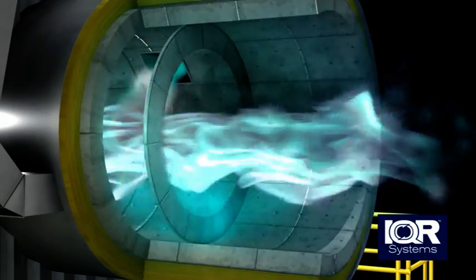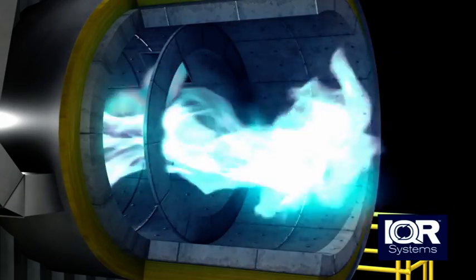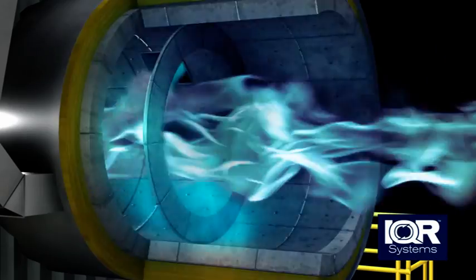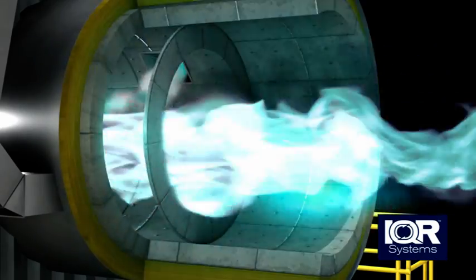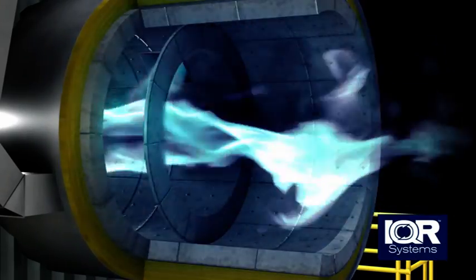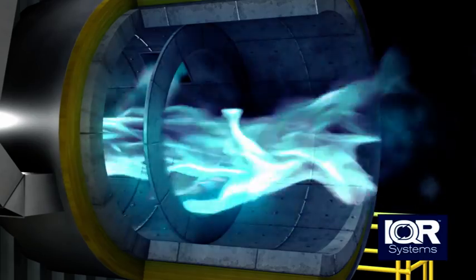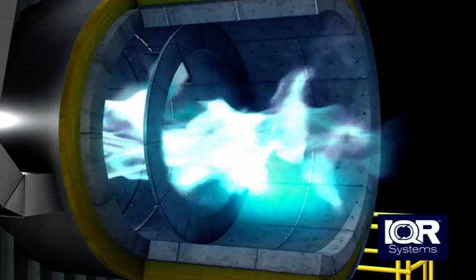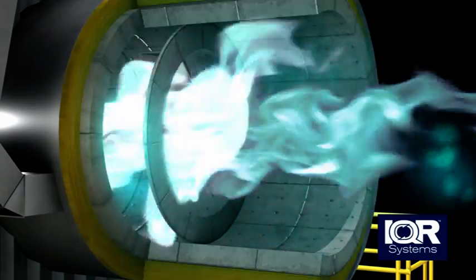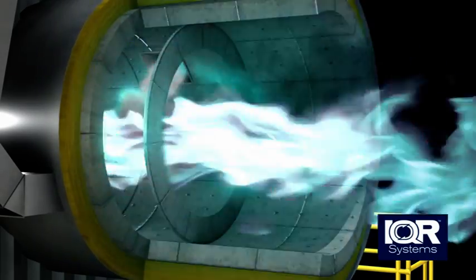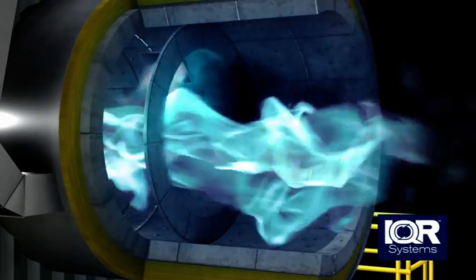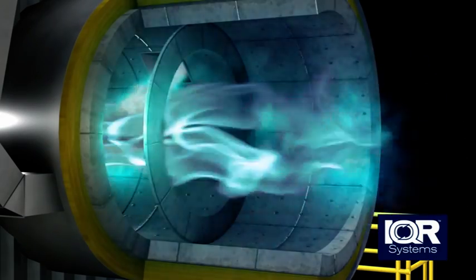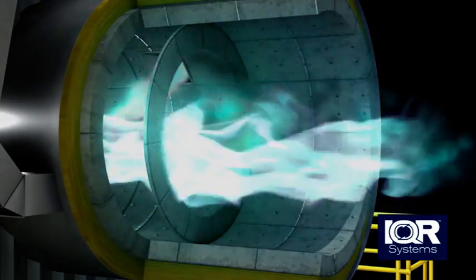Now energy can be extracted from the gasifier. QR's patented burner construction assures a recirculation of uncombusted gas to the ignition point. Combustion in a separate burner allows very good combustion values. 24 hour mean values of carbon monoxide can, even at 10% load, be kept at less than 20mg per cubic metre flue gas.